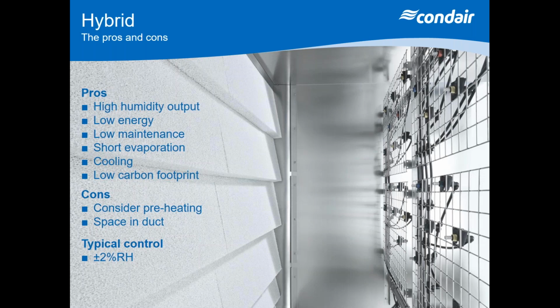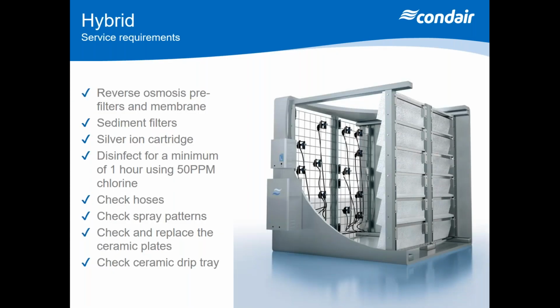You will have to change the nozzles every so often to make sure they're spraying correctly. Also, you can have a silver system. The silver dosage system would have to be replaced every so often. That's normally on a counter on the display of the cabinet, and that will need to be replaced.